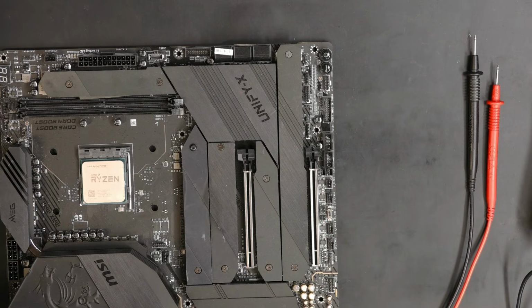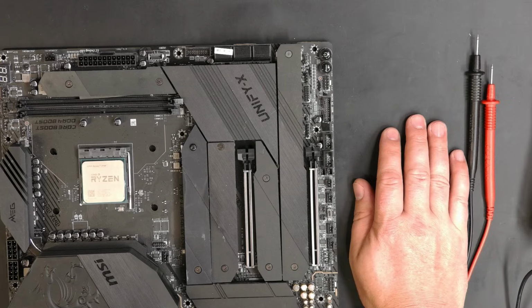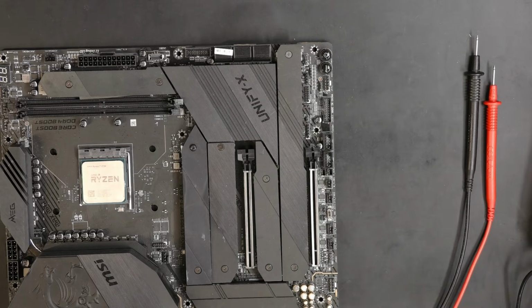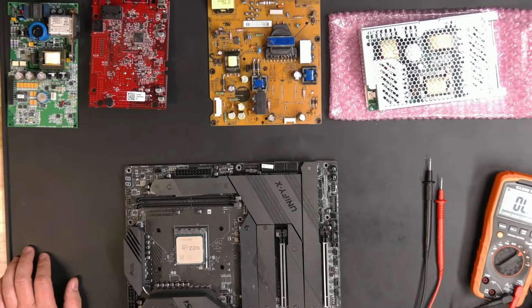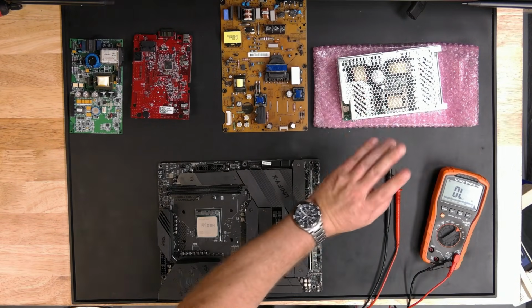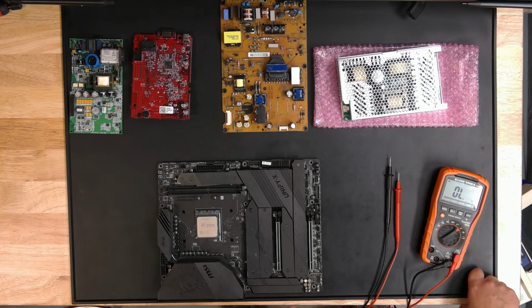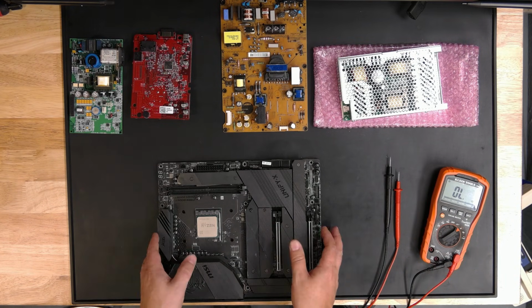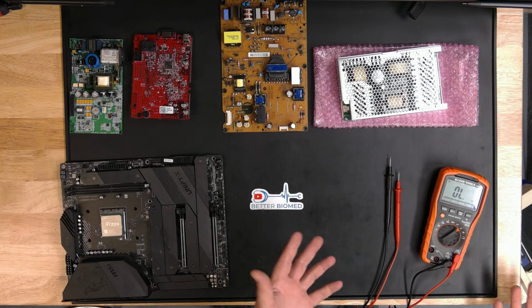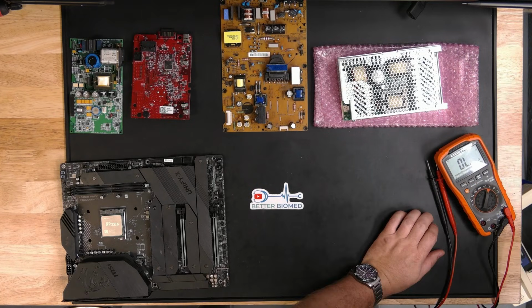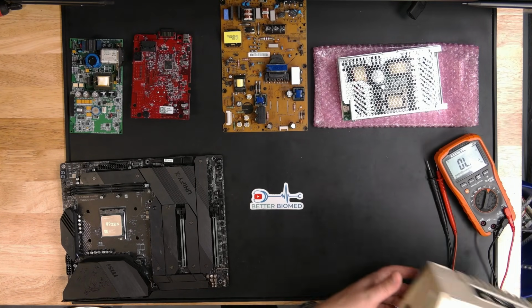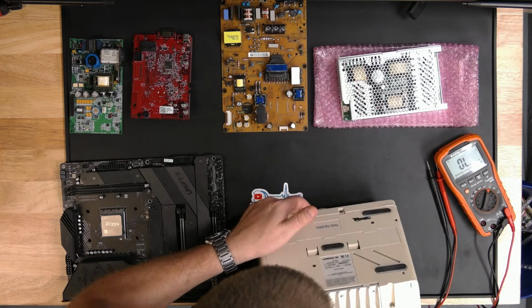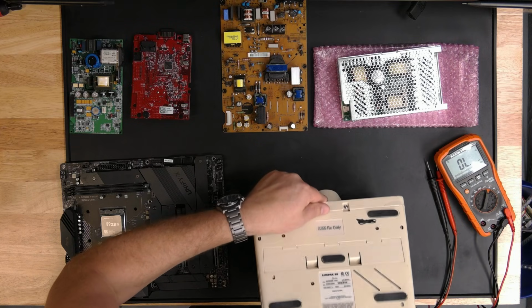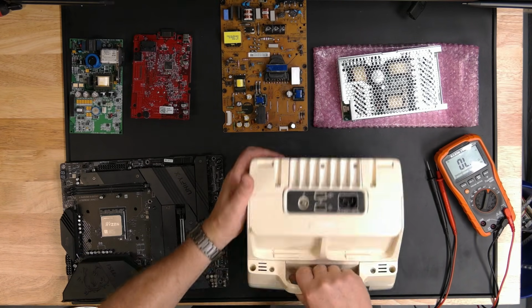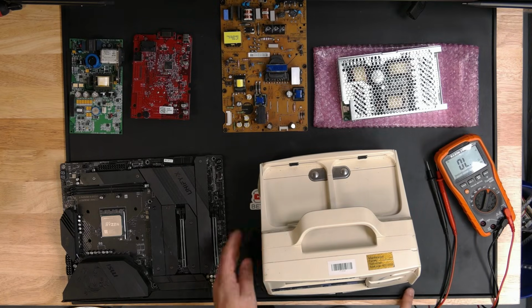But folks, that's just a semi-brief video on the importance of ground. Medical devices do have a much different ground system. And the DC side of a medical device is often not grounded whatsoever. And in fact, that's why many DC devices that are medical have plastic cases, because they don't want the case of that device to be referenced to ground, because that's a shock hazard. So you'll see double insulated on many devices. This guy right here, it's got an external ground point. See it right there. And it does have internal ground. Man, I wish I could tear this apart for you guys to show it. But anyway, there you have it.